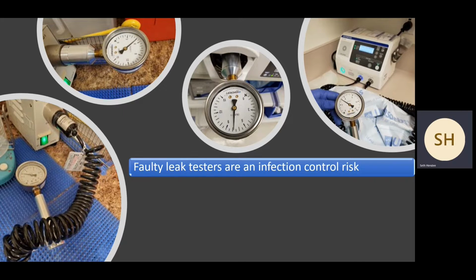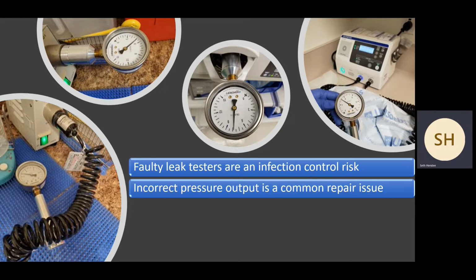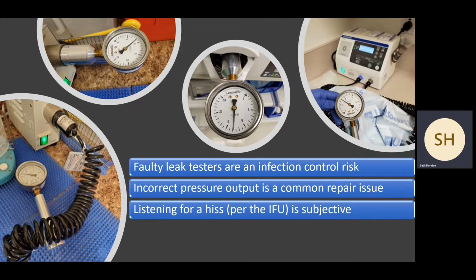And here are some things to think about. A faulty leak tester is an infection control risk. You will not see small leaks when you start to have pressure problems. And if you don't catch a small leak, it is still a leak in an endoscope, and it can still cause fluid invasion. So it's an infection risk. Incorrect pressure output is a common repair issue, and these units, most of them can be repaired, or in the case of, say, the Olympus MU1, that black cord that you see there, the MB155, that's considered a consumable by Olympus. So they would tell you, you may have problems with this cord, you should buy a new one. So that again tells you that they're subject to wear and potential damage where they would have to be replaced.